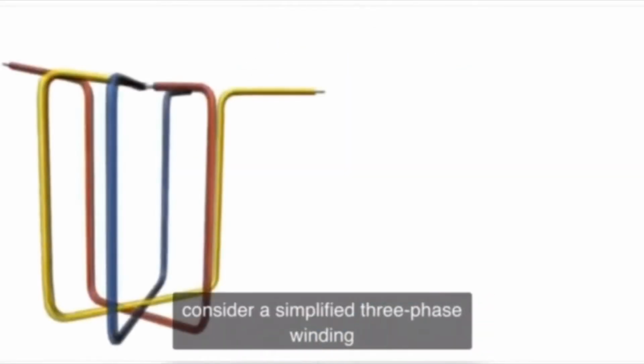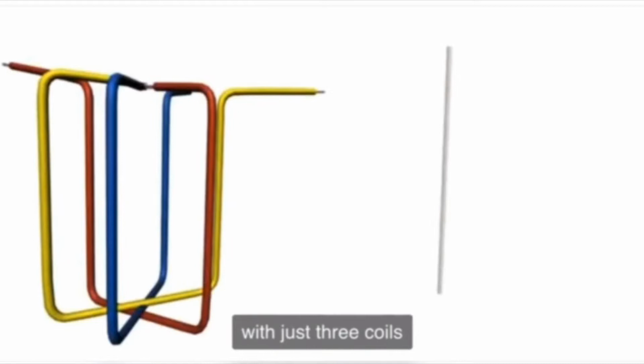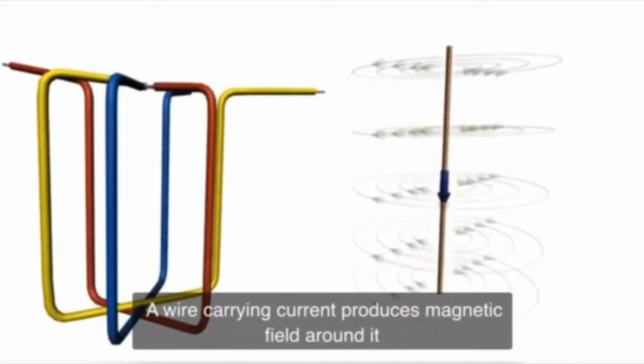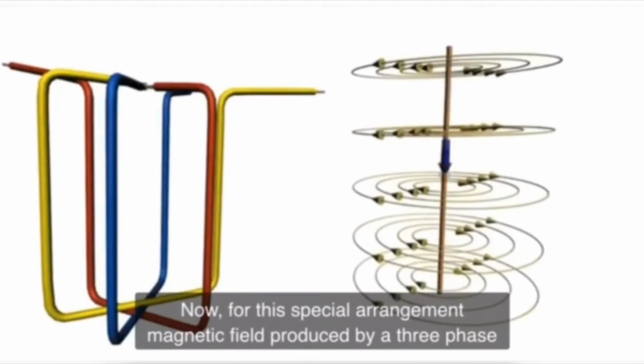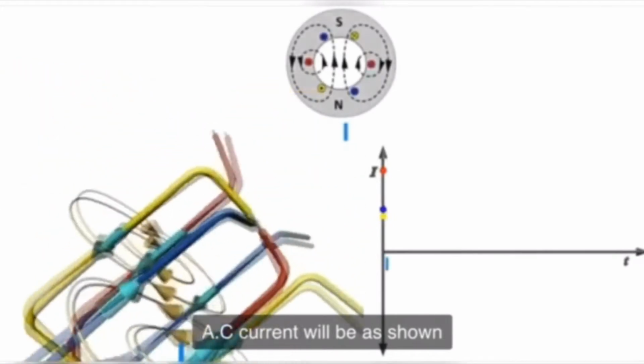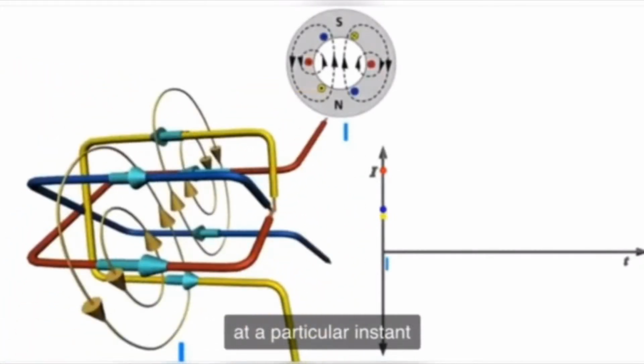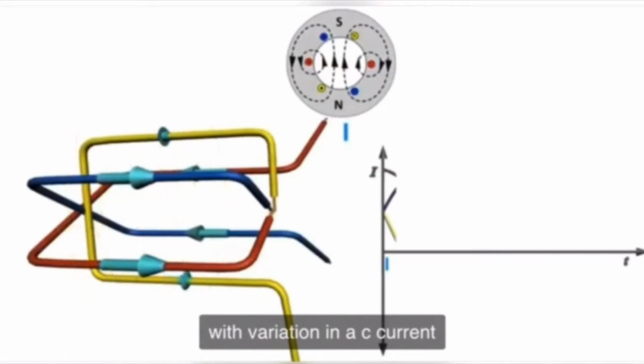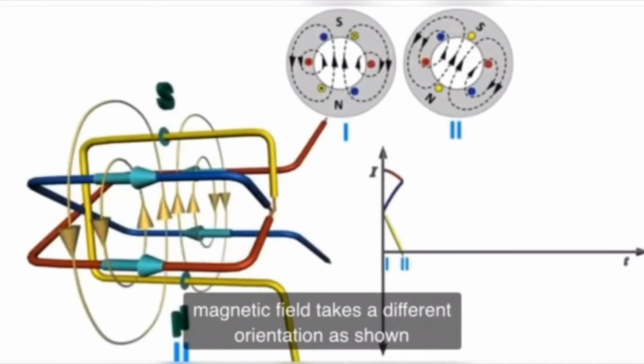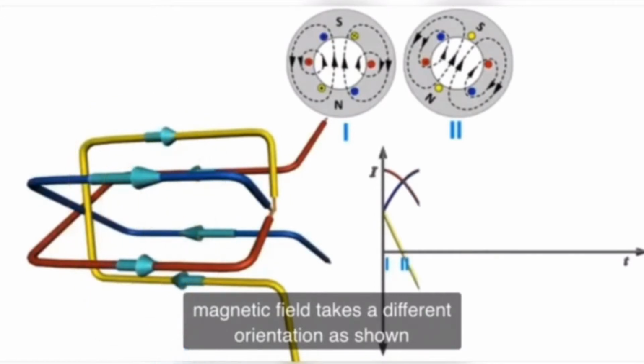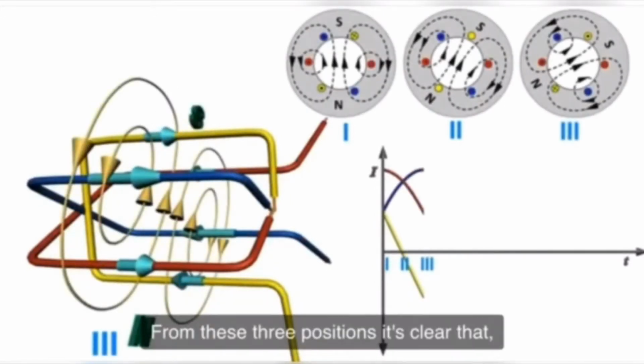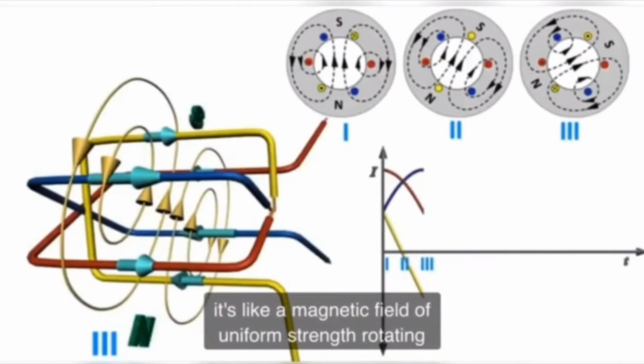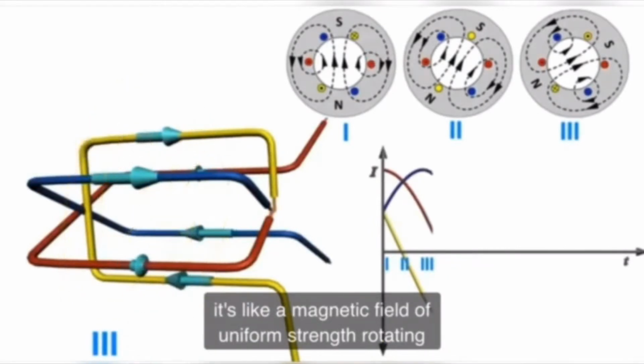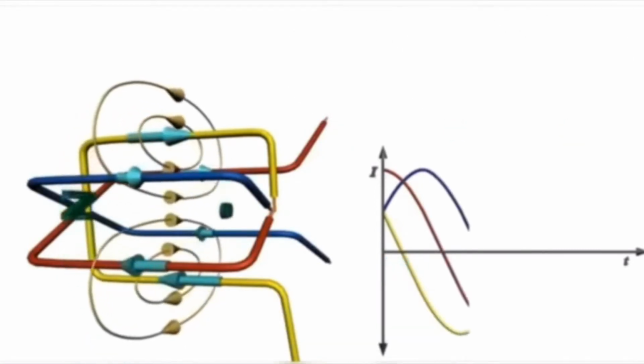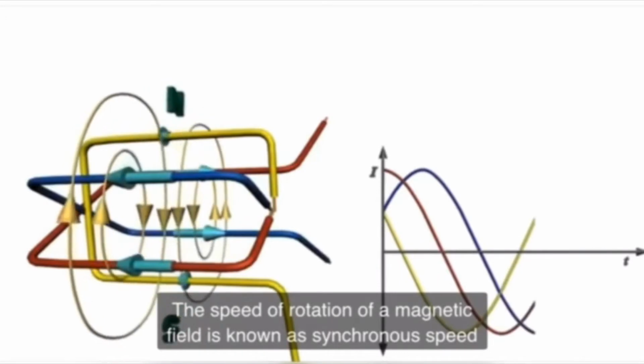Consider a simplified three-phase winding with just 3 coils. A wire carrying current produces a magnetic field around it. Now, for this special arrangement, the magnetic field produced by three-phase AC current will be as shown at a particular instant. With variation in AC current, the magnetic field takes a different orientation as shown. From these 3 positions, it's clear that it's like a magnetic field of uniform strength rotating. The speed of rotation of a magnetic field is known as synchronous speed.